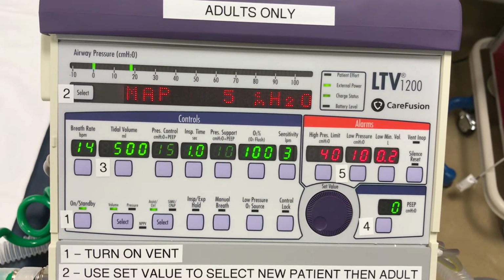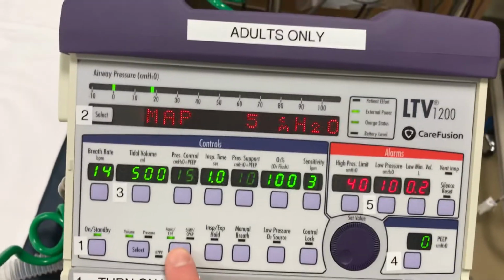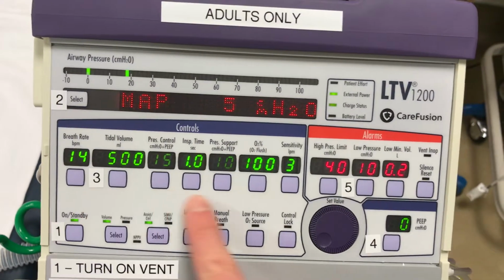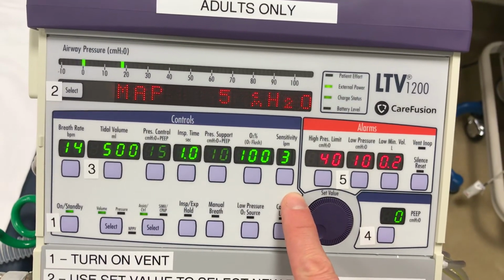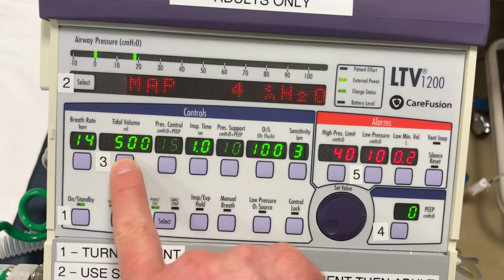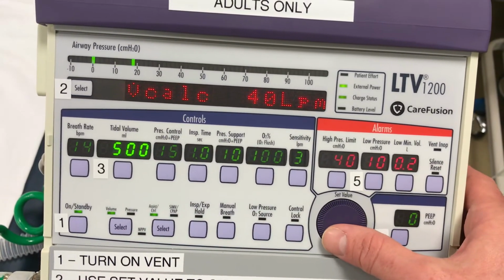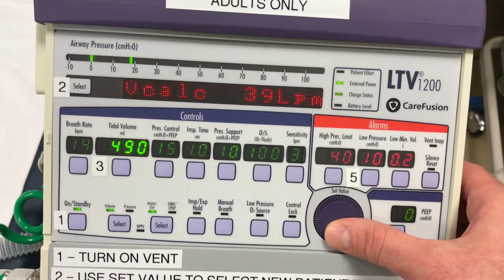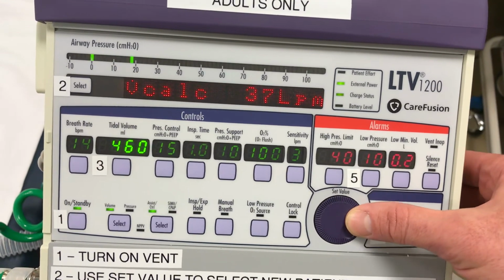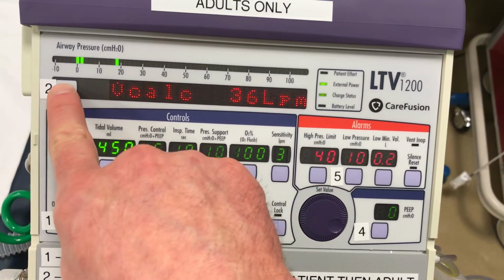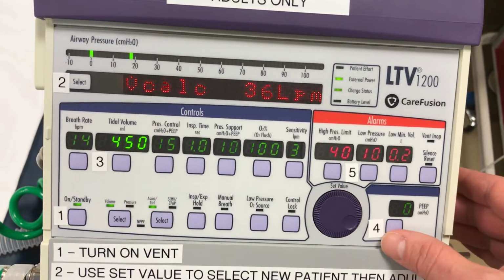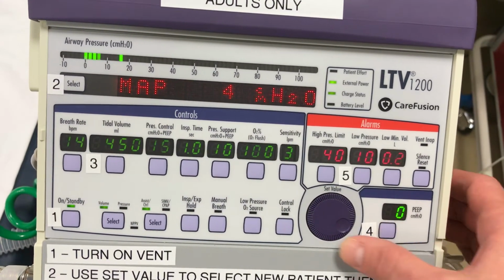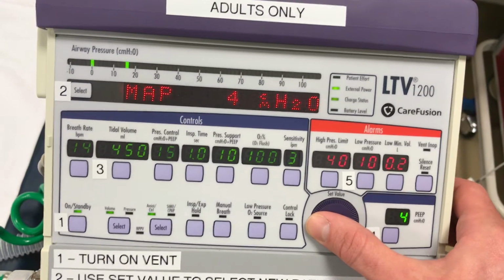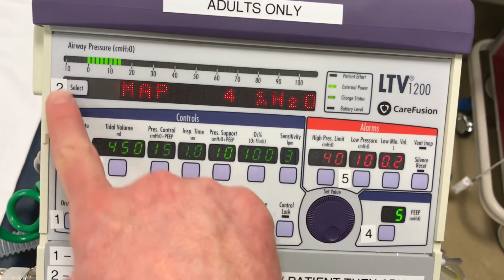You'll notice we are currently in an assist control mode, and the brighter numbers are the numbers that we're able to manipulate. If I want to decrease my tidal volume, I push tidal volume and then rotate the set value dial until I get my desired volume and hit select. Similarly, to increase PEEP, you hit your PEEP, increase your PEEP, and select.